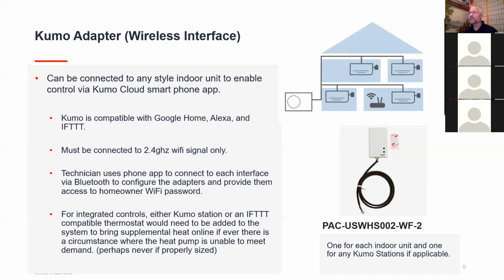Okay, at this point in time, the Kumo adapter only works with 2.4 gigahertz wireless signals. A lot of new modems have both a 2.4 gigahertz and 5 gigahertz band. So when you're setting it up, you need to make sure that the technician's phone is only connected to that 2.4 gigahertz zone, and that you're only connecting it to the zone and the password, the channel that's associated with that 2.4 gigahertz band. And then, once your phone's connected, you basically communicate with the adapter via Bluetooth on your phone to configure the system and tell it what the Wi-Fi password is so that it can connect to the Wi-Fi independently.